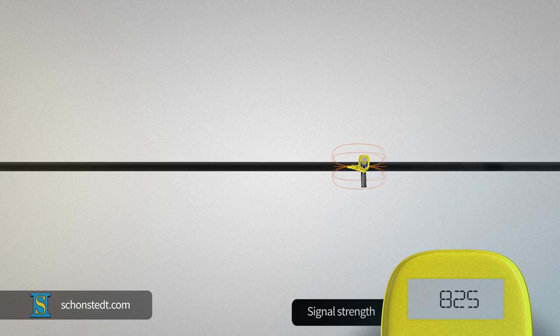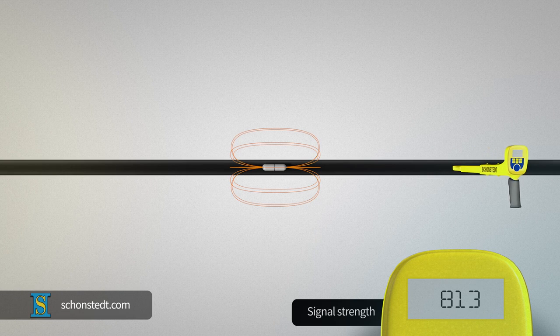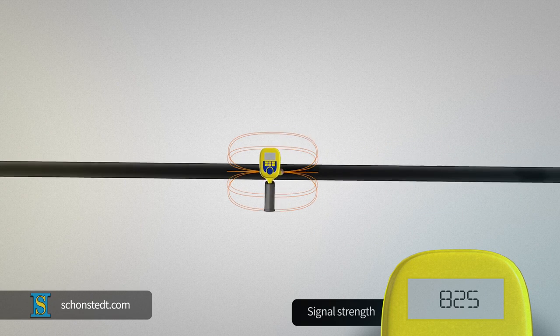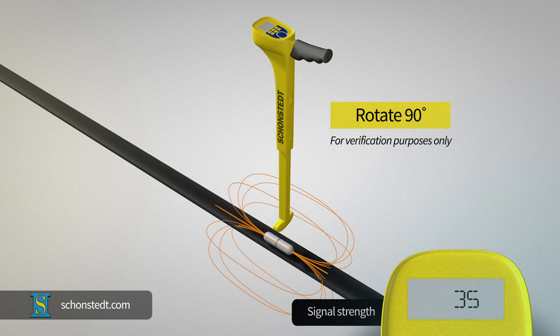When you move past the sonde location, the signal will start dropping again, giving you a general idea of the sonde's location. You can move back to find the strongest signal and, at that point, rotate the receiver 90 degrees, verifying that the signal drops significantly to a null.